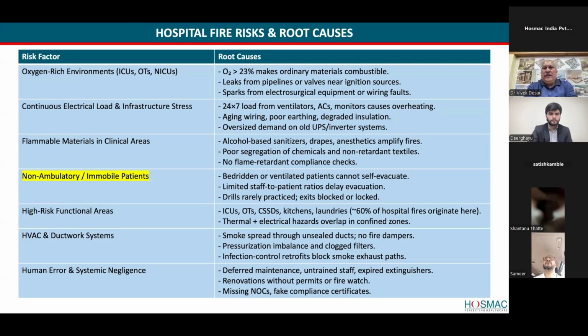Okay. And this earthing, can you just elaborate anything about earthing? Earthing, see, we should understand what earthing is first. We call it body earthing. All medical equipment and all electrical equipment are earthed. Earth means that any loose phase or leak current which happens in any medical equipment, if it touches any surface, it will short circuit, or if somebody touches that equipment, they will get a shock. So that current gets earthed to the earth pit directly. For each and every medical equipment, we have a separate dedicated earthing. For HVAC, we have a separate dedicated earthing. Normally people combine the earthing pits. It should not be done. Each and every individual equipment should have a separate earthing for safer control of the earth leakages.